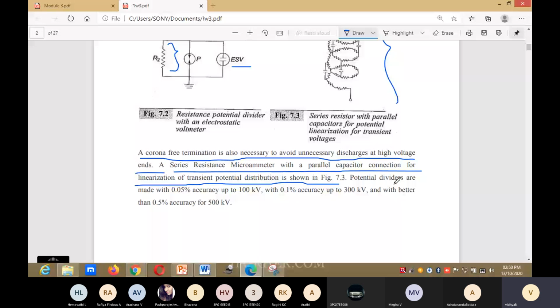Potential dividers are made with 0.05% accuracy up to 100 kV, 0.1% accuracy up to 300 kV, and better than 0.5% accuracy for 500 kV.